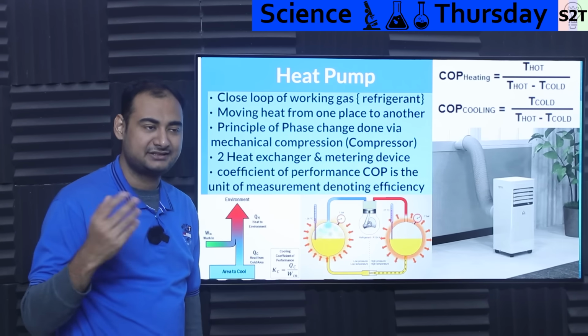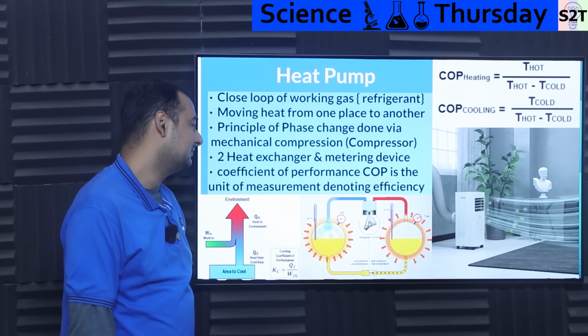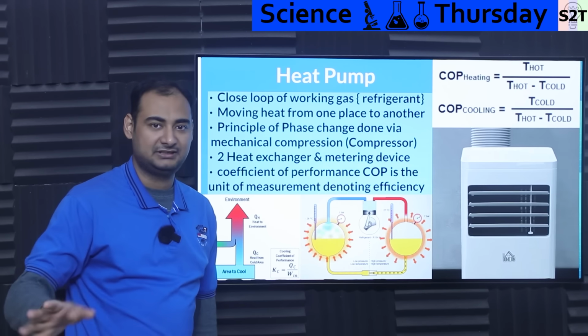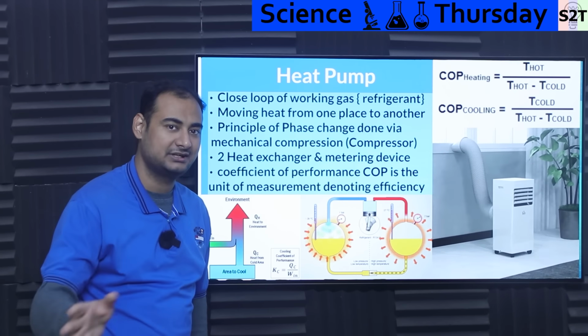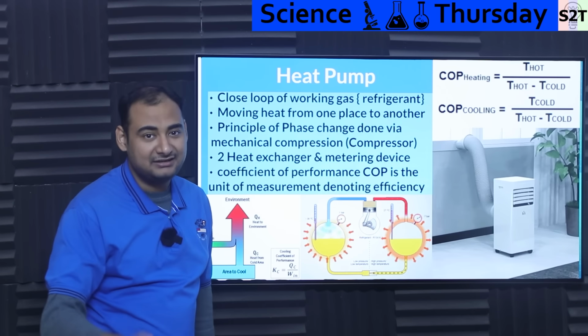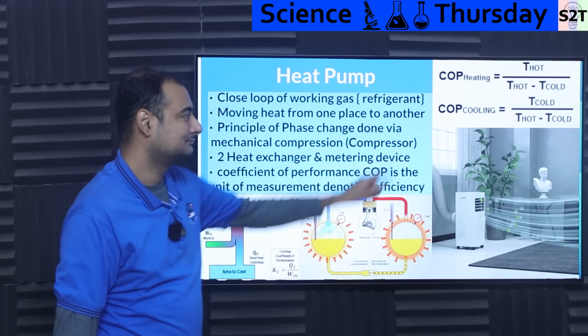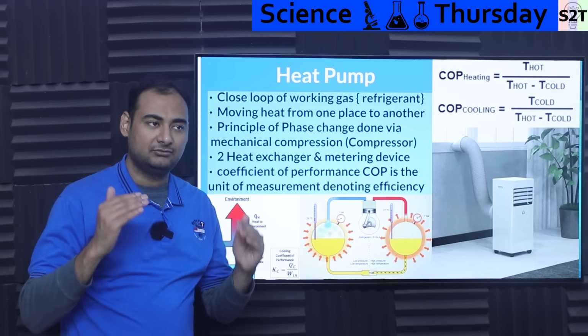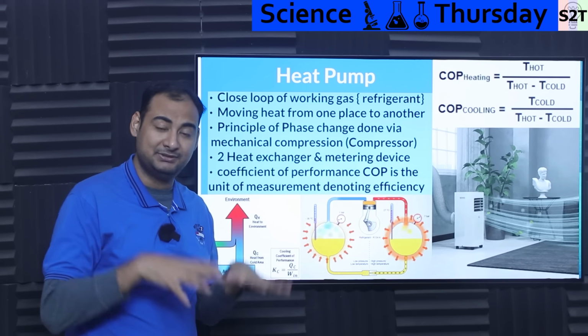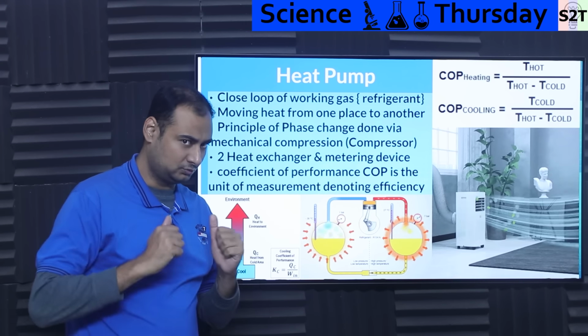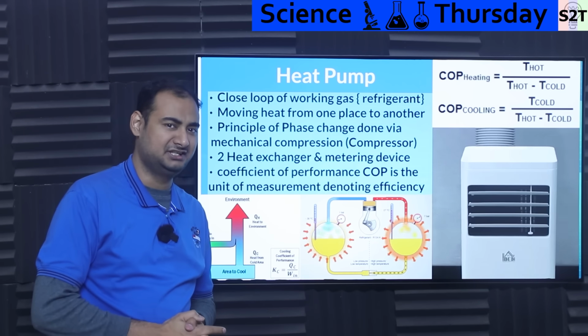Heating, awesome. Heating generally is 1 COP plus. So if a system is rated at a COP of 5 in both directions, it simply means you are getting 4 units of cooling and 5 units of heating. So coefficient of performance generally works that way. And again, 2 is the bare minimum. If you are below 2, it's not that good. 3, really good. 5, 6, damn.